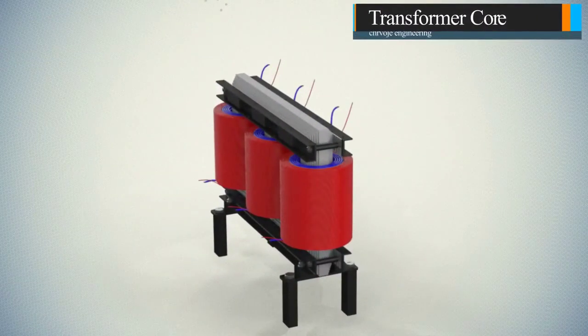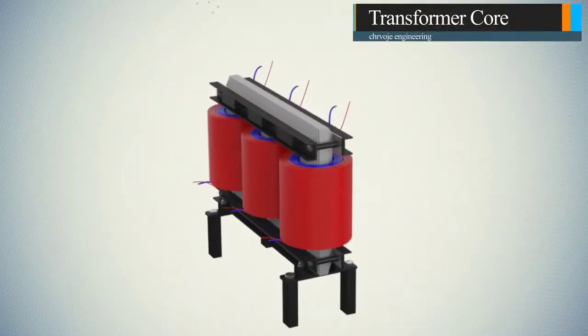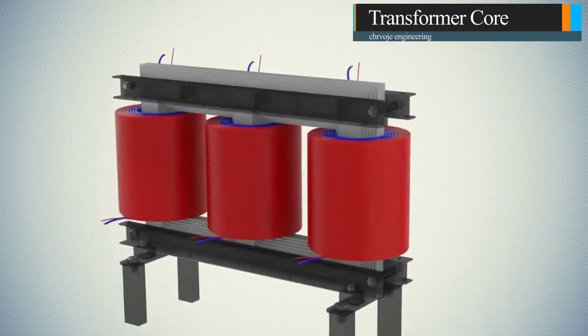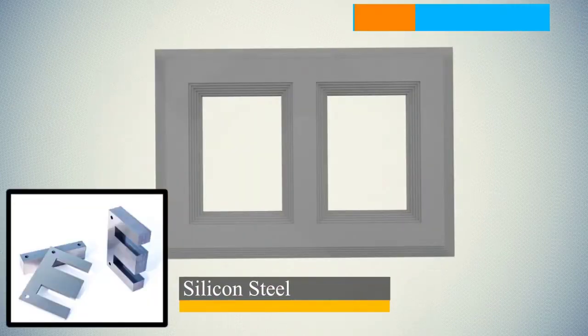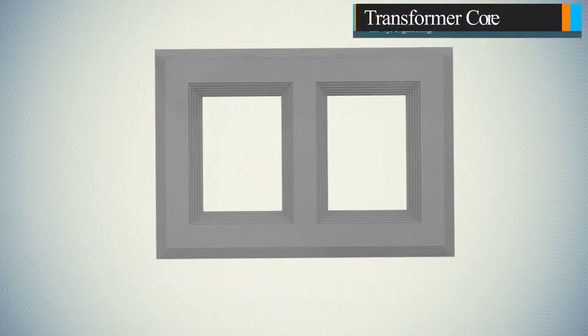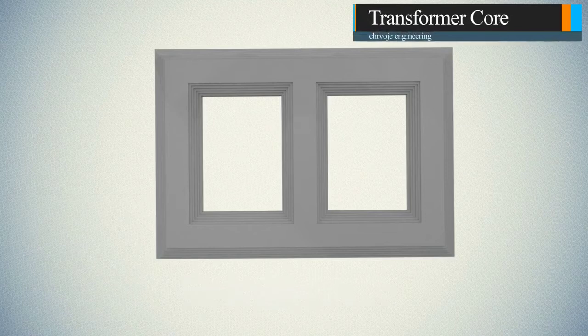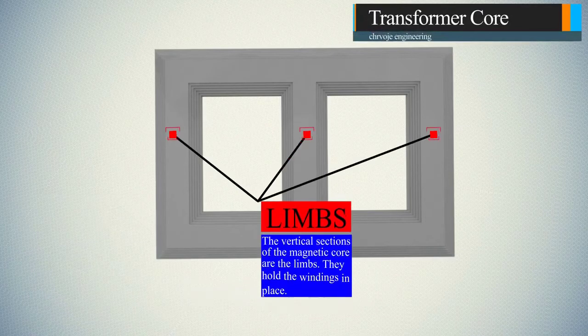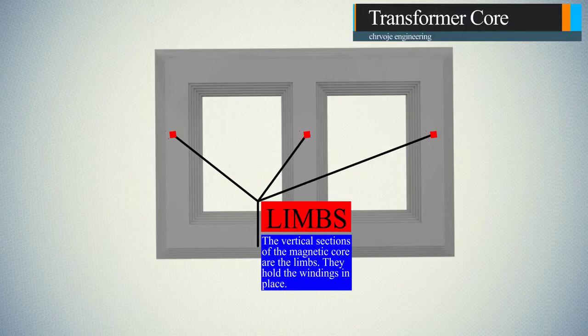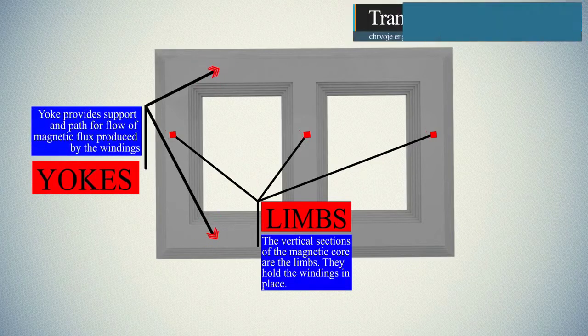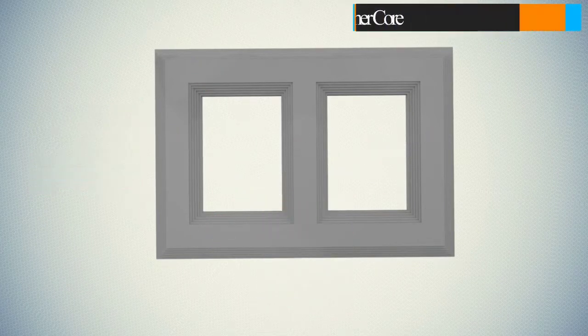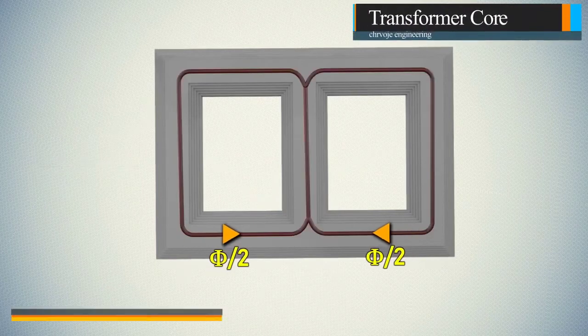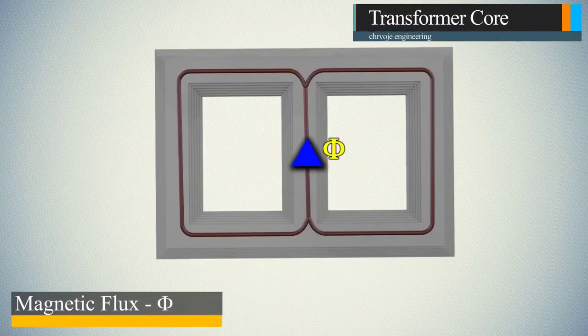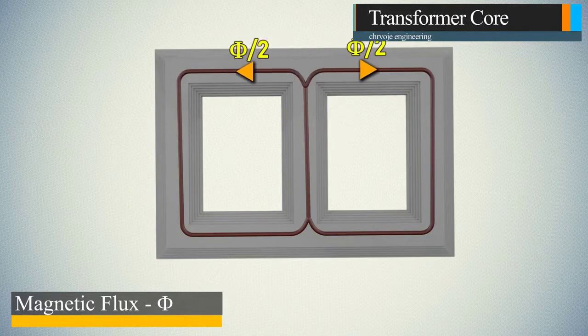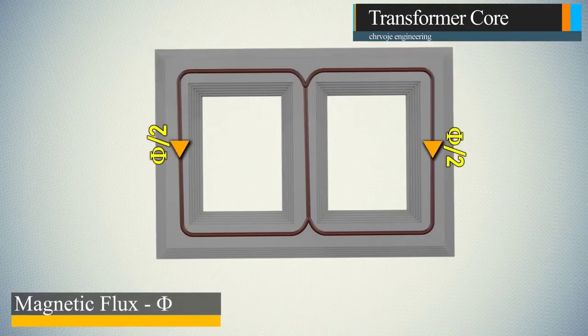As we say, the transformer core is the heart of any transformer. The material used for the construction of a three-phase transformer core is silicon steel, which has high permeability. The core of the three-phase transformer is usually made up of three limbs in the same plane and two yokes, which are the horizontal parts of the core. The transformer core is designed to provide a path for the magnetic flux to flow around, which is necessary for the induction of the voltage between two windings.